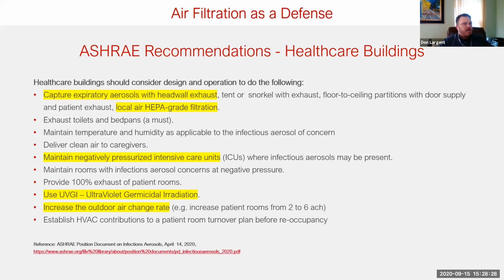So ASHRAE recommendations for healthcare buildings: capture the expiratory aerosols with the headwall exhaust. I'll show an application of that with the airborne isolation infection room, negative pressure isolation setup. Local air HEPA grade filtration if possible. Maintain the negative pressure in intensive care units. Again, use of the UVGI upper room as well as kill on the fly. And again, increase the outdoor air exchange rate, more fresh air intake.